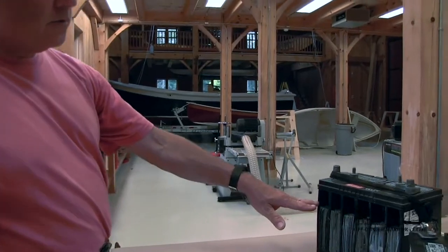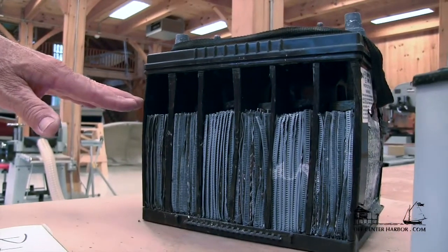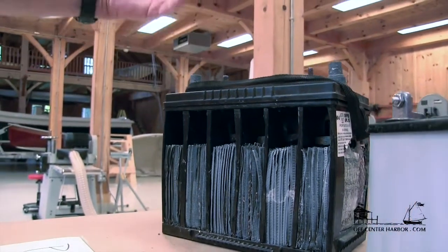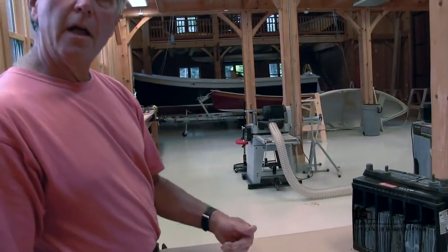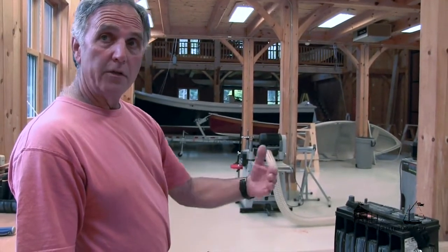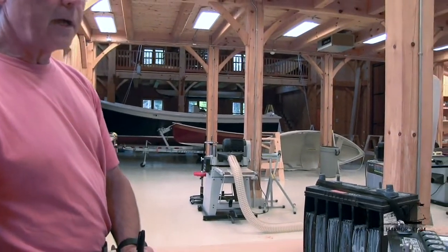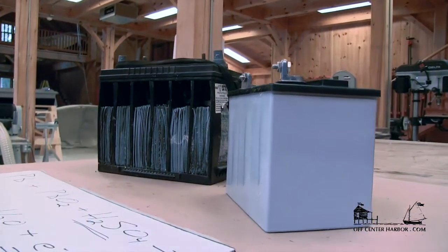As opposed to our traditional flooded battery — most of you may be aware that if the level goes down inside the flooded battery, you would add just pure water, usually distilled water. That's the only thing we lose in this chemical reaction: H2O. That's all we want to add back to the battery. But an absorbed glass mat battery or a gel cell battery both eliminate the need for any of that servicing, as they're both completely sealed.